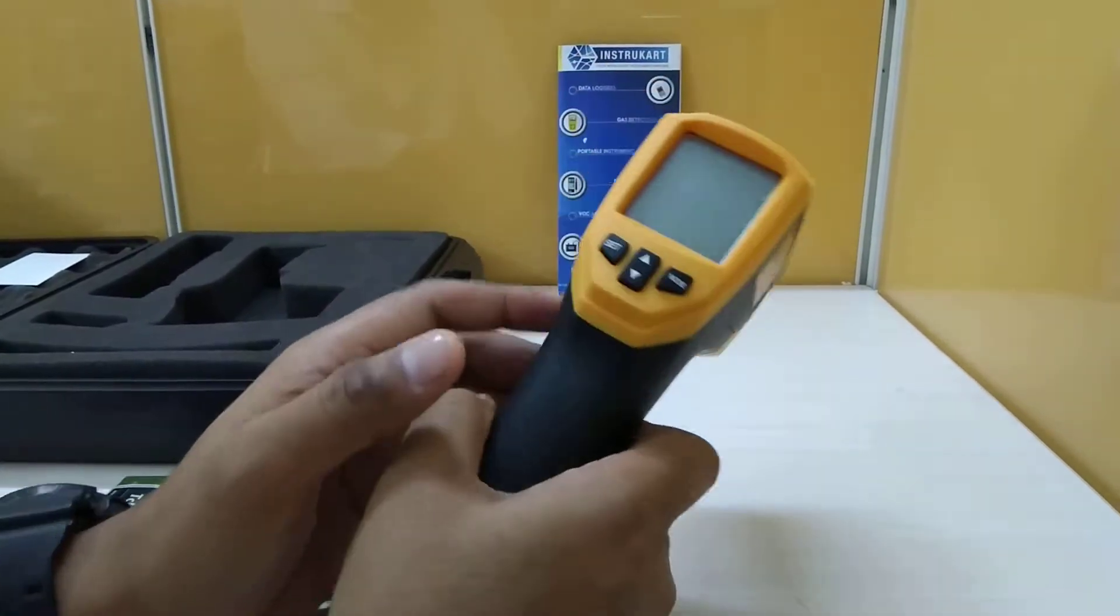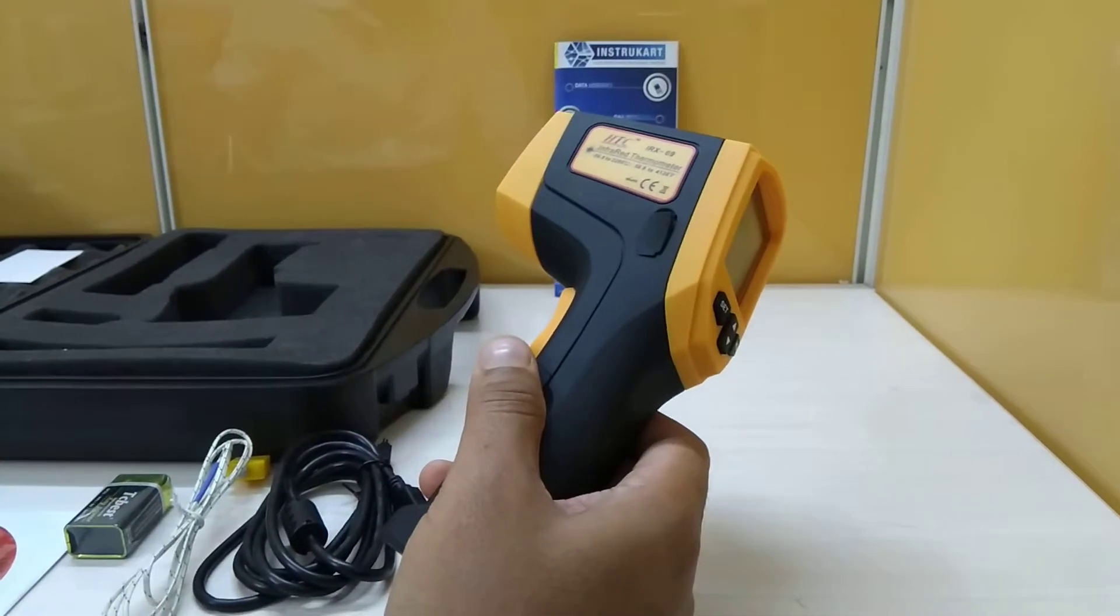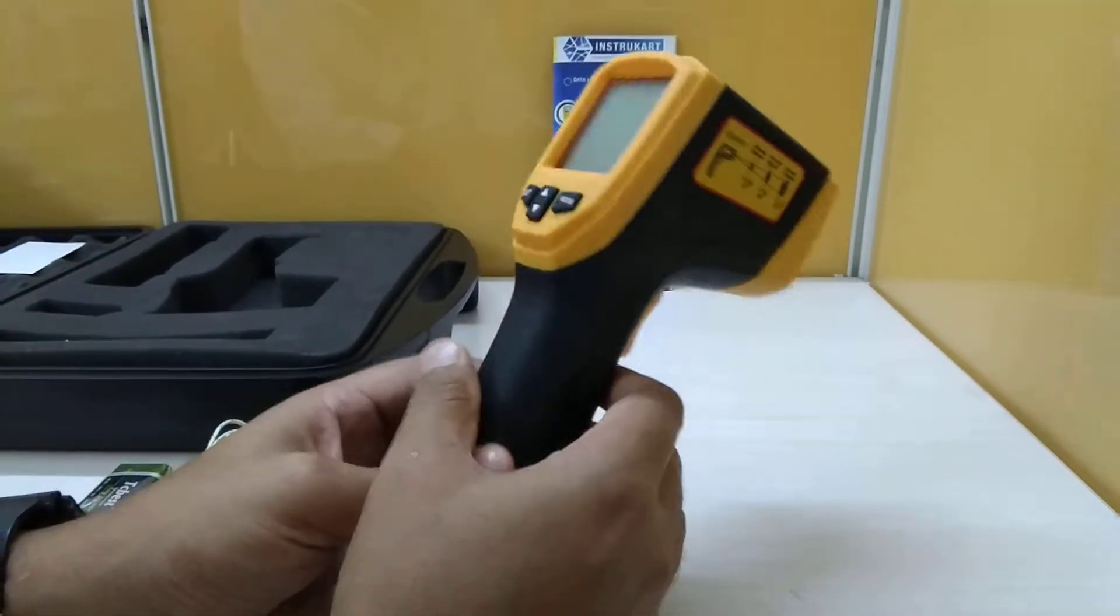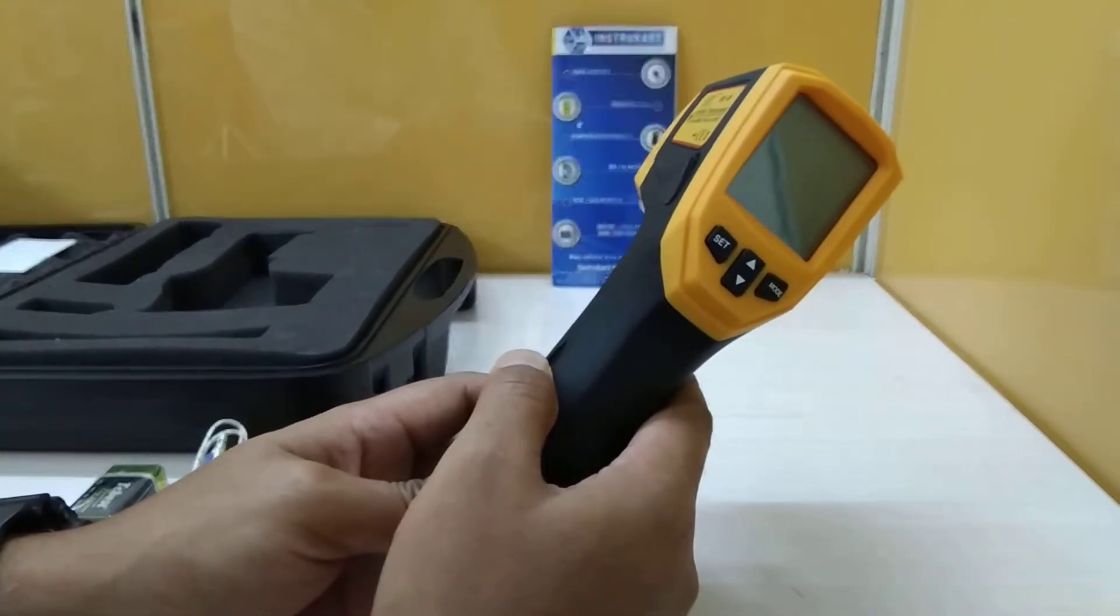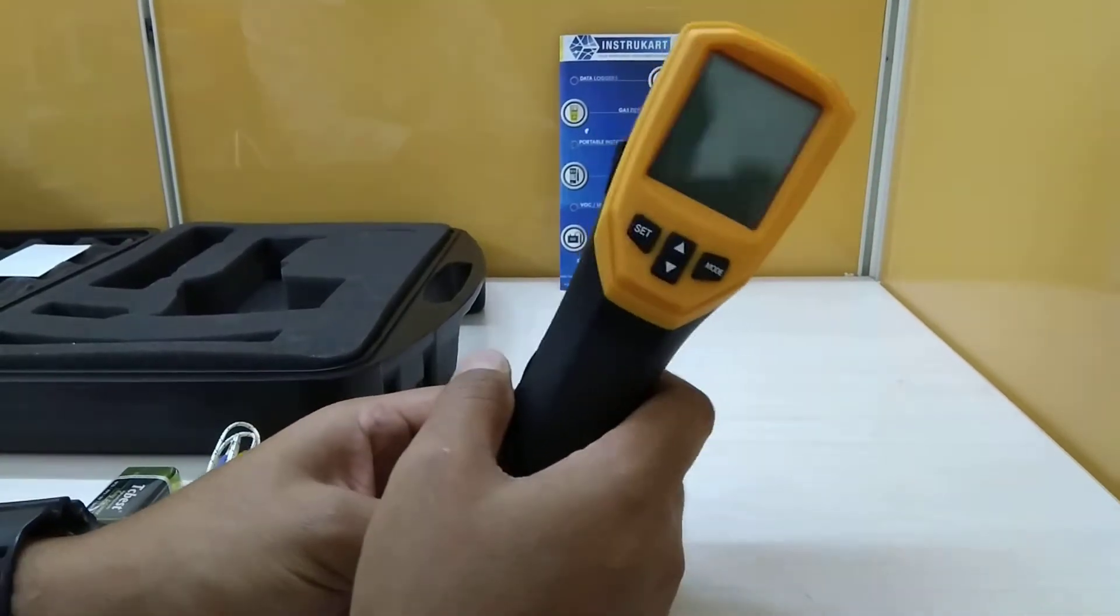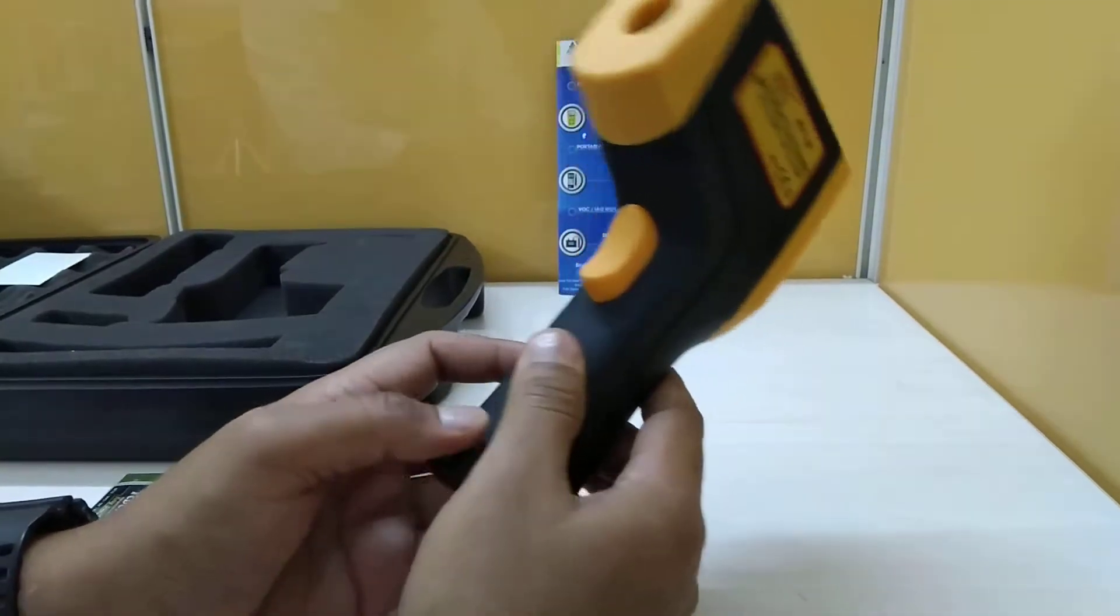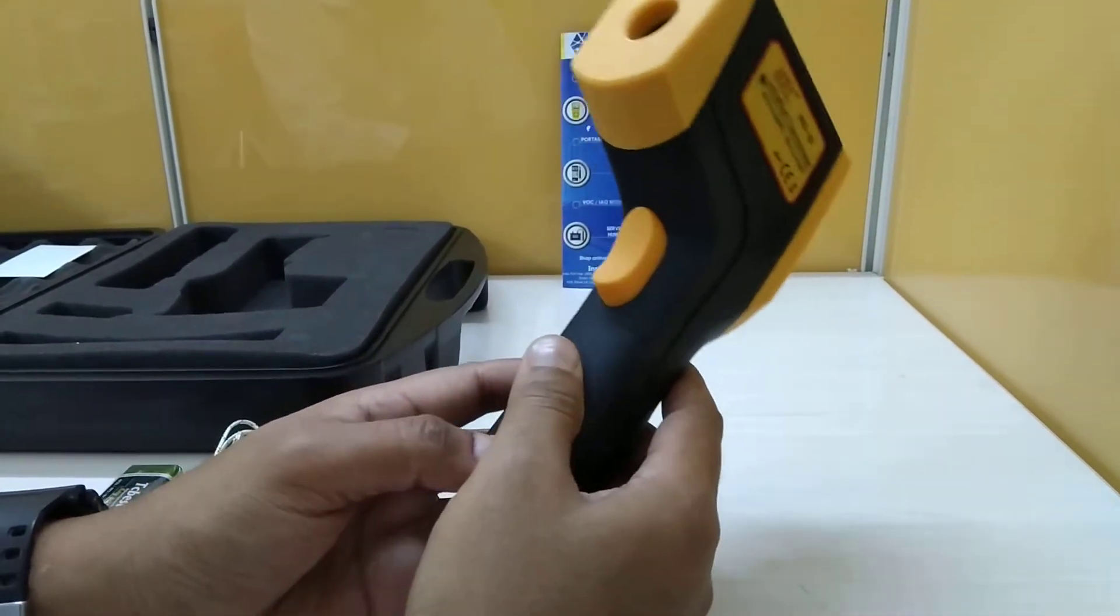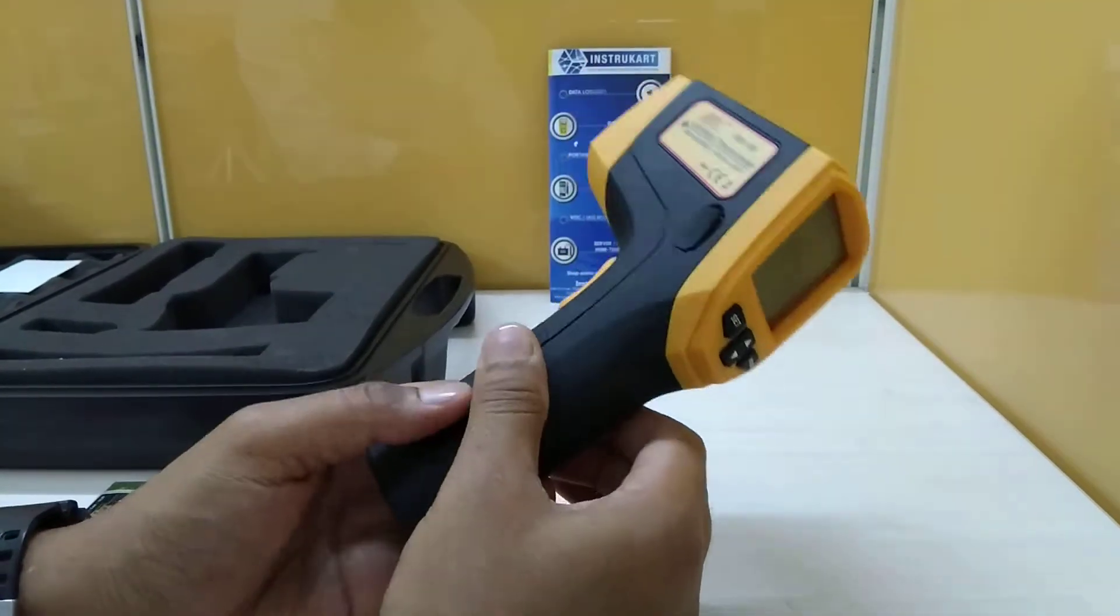Now this particular infrared thermometer has got an accuracy of plus or minus 4 degrees Celsius from minus 50 degrees to 0 degrees Celsius. Up to 500 degrees Celsius it has got an accuracy of 1.5 percent of reading, and above 500 degrees it has got plus or minus 2 percent of the reading.